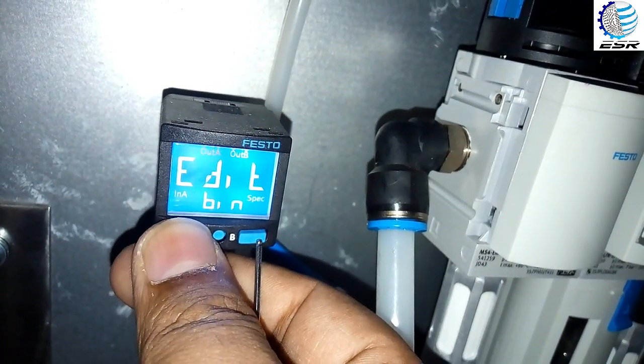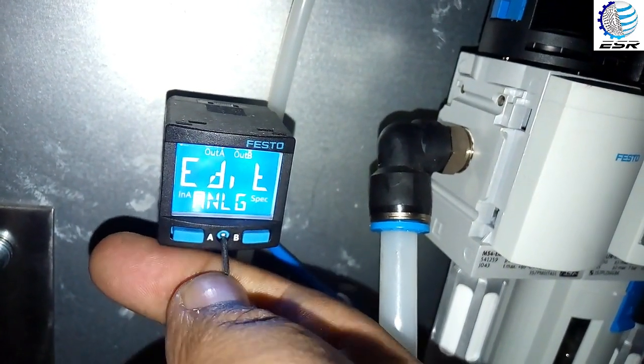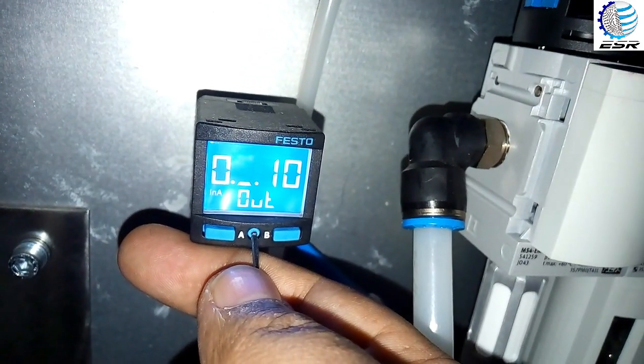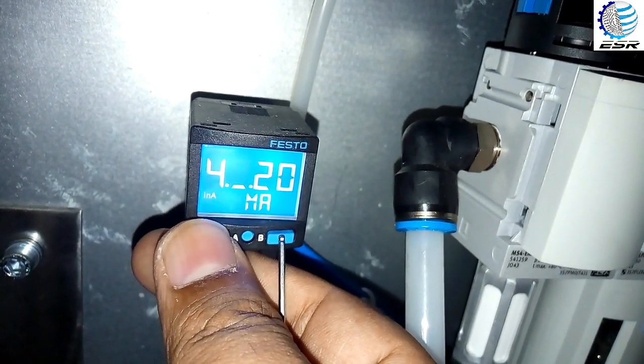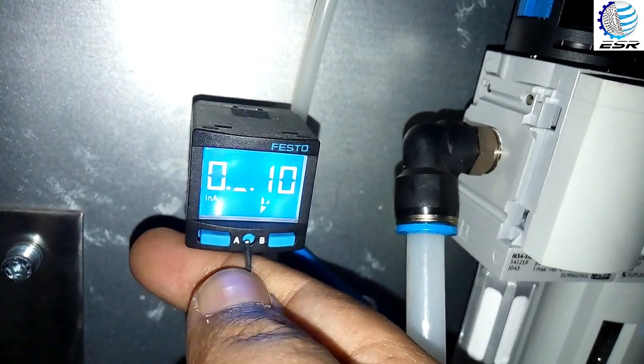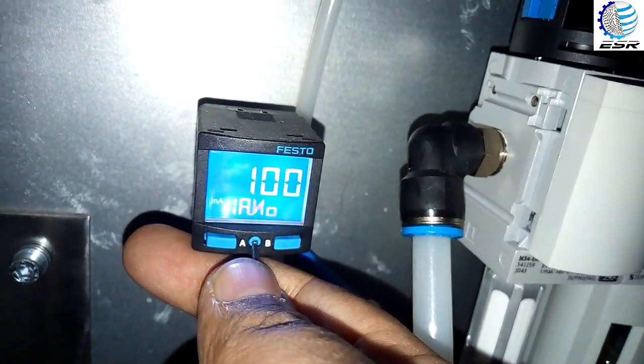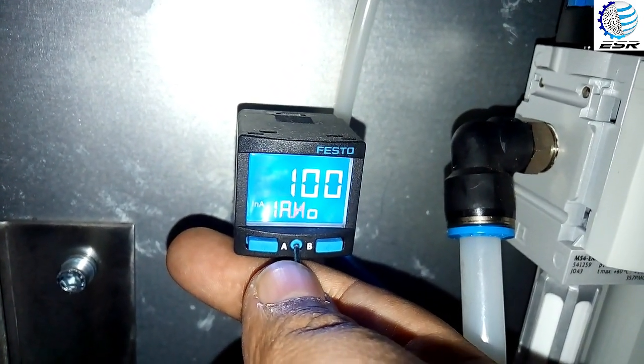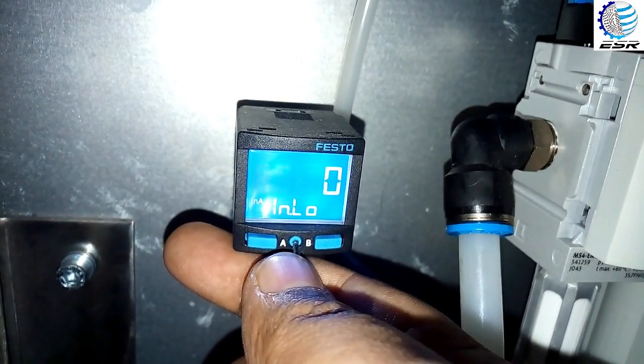Now we will move to the analog output menu. In this menu, the output is in volts and it is set to 0 to 10 volts — you can change it according to your requirement. Hi percentage is 100 and the low percentage is 0.